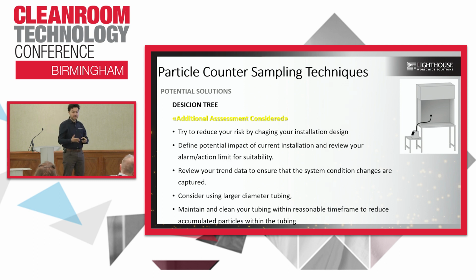And define the potential impact of the current installation and review your alarm and action limits for suitability, which means you can consider changing your alarm and action limits depending on your risk, and you can make a side-by-side engineering comparison with a portable device to see how many particles you are losing throughout the process. So it also changes the limit. And review your trend data to ensure that the system condition changes are captured. The idea here is to capture the risk conditions. If your trend data will not show you all the risks associated with the particles, then you are at risk.